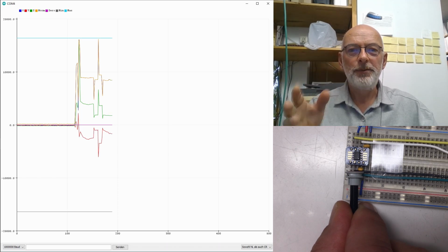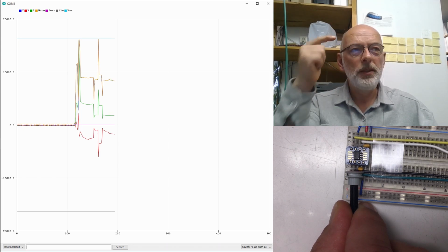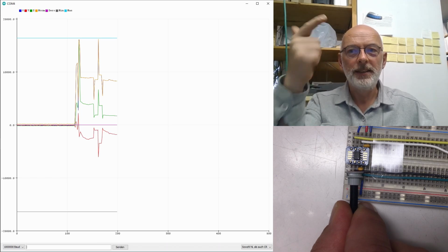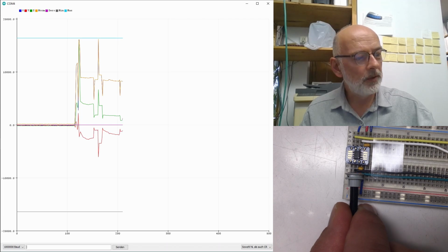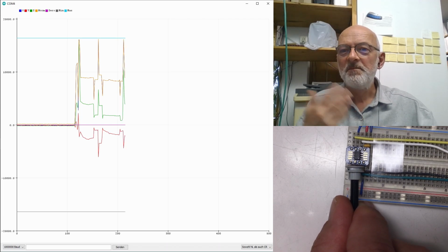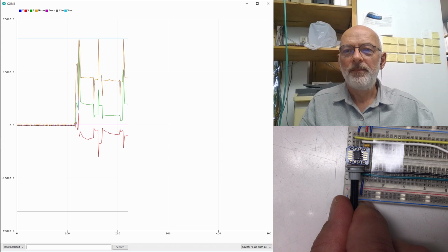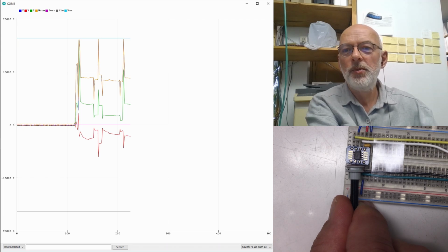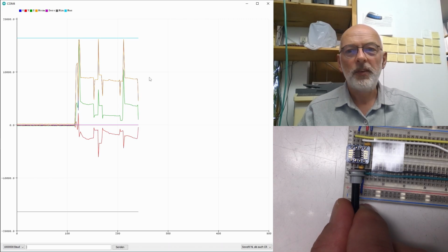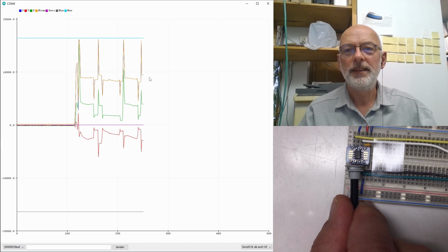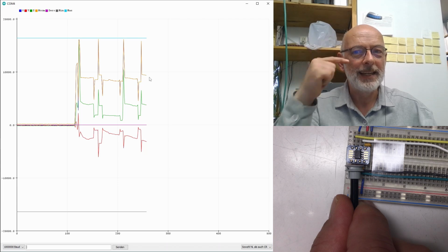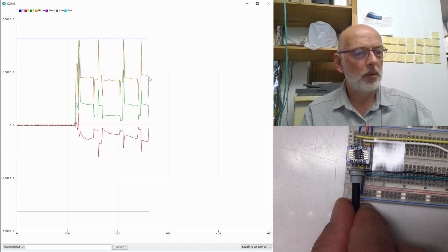With the difference that we don't just do get, we do get, knob, wait half a second, get, knob, wait half a second. And the automatic gain control seems to work exactly like before. It always tries to get to this sweet spot level of around 50% of full scale. So I think the datasheet is wrong in that respect, that the gain control really needs get to work properly.